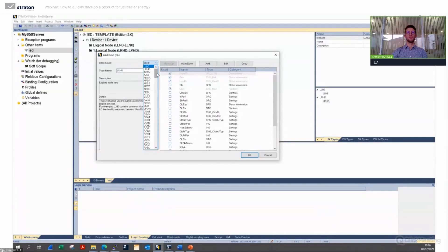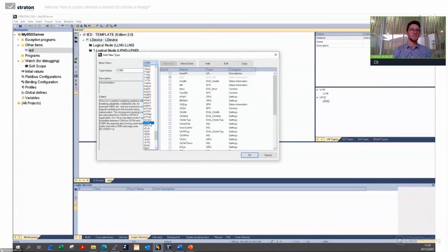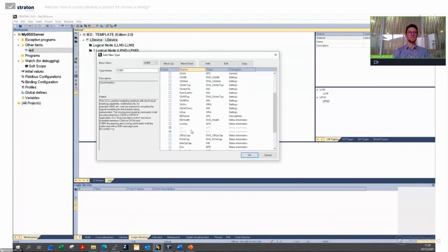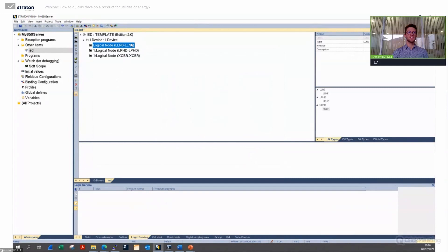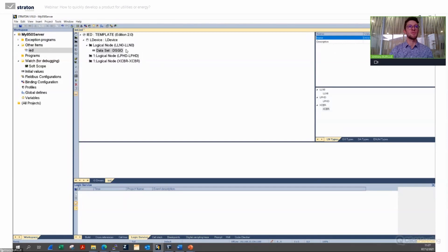We add Logical Node Zero, then LPHD — the general device information. Now we need a circuit breaker: I click to create a new logical node. If you are familiar with the standard, circuit breaker logical nodes start with X. Typing X on the keyboard we see circuit breaker XCBR — and here a few data objects are already checked as mandatory ones. We will take the position — it's already checked — and we will make it blink.